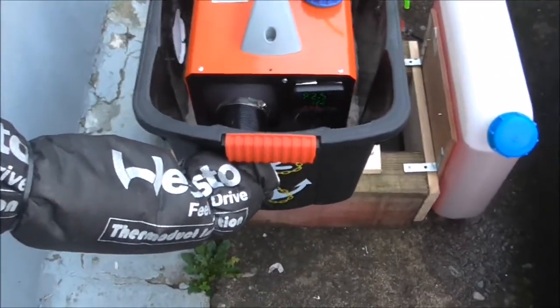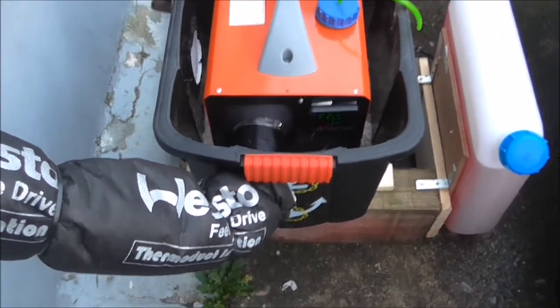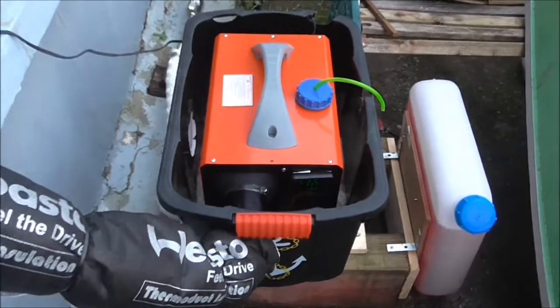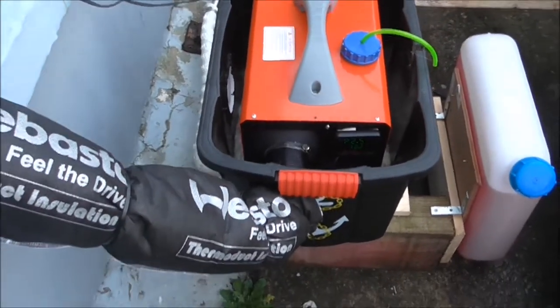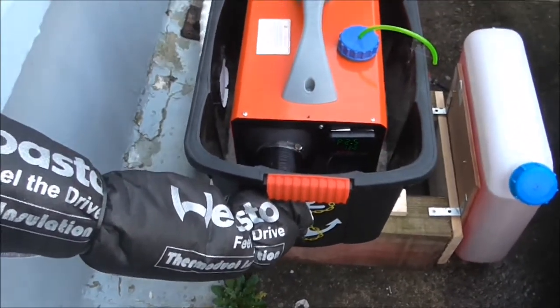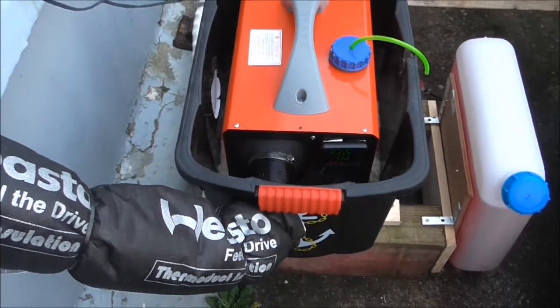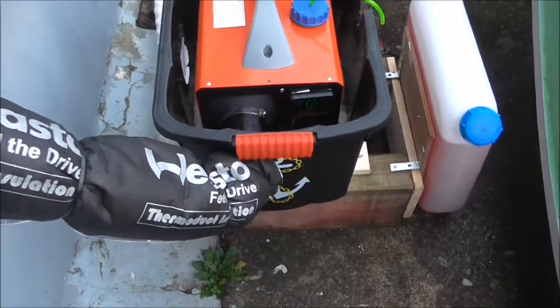I put in an external tank and it was working away fine until yesterday evening when it went away. A couple of hours later I realised there was no heat. I came out here and it had the dreaded error code. Tried a few times — white smoke and it's shutting down.